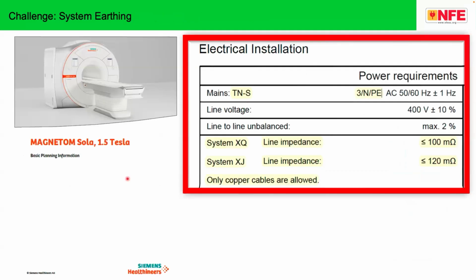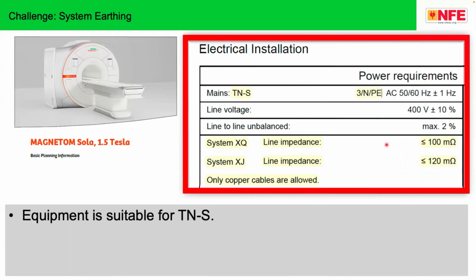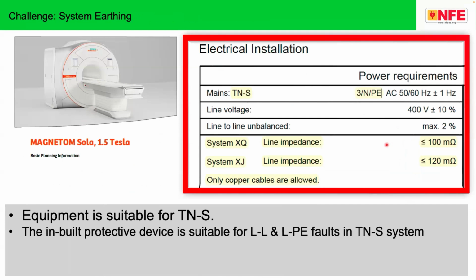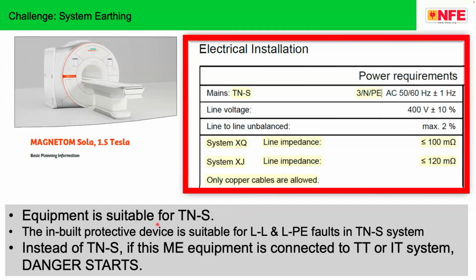Please stop using this. This particular equipment, as I showed you, is for an electrical installation, TNS system. Now the line impedances are very much known. This equipment is suitable for TNS. This means the fuse inbuilt into this device is capable of automatic disconnection in case of a line to line, line to neutral, or line to earth fault, because you have to keep the impedance lesser than this value. So the fuse inside the equipment is efficient to disconnect in case of a fault. Unfortunately, instead of TNS, this medical electrical equipment is connected to a TT or IT system, and the danger starts there.